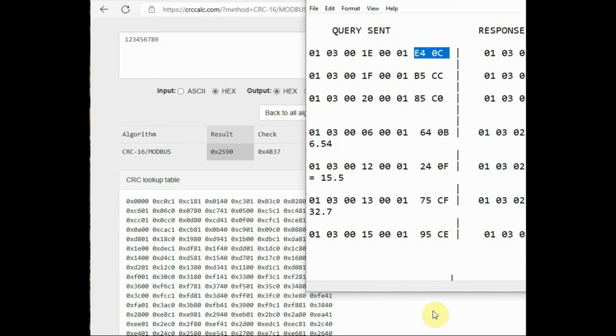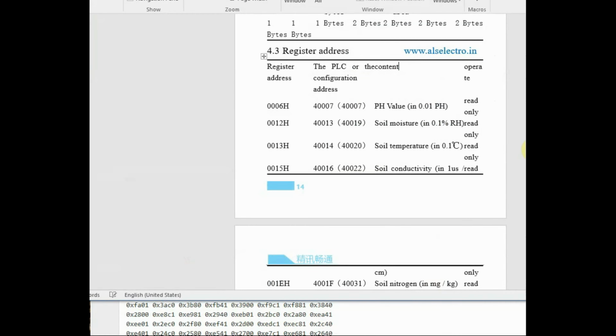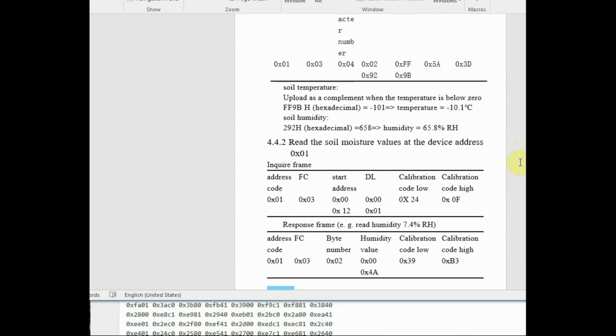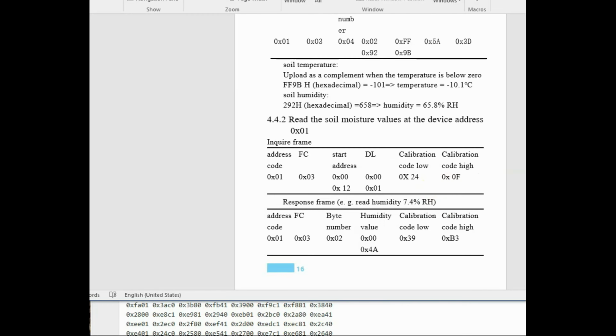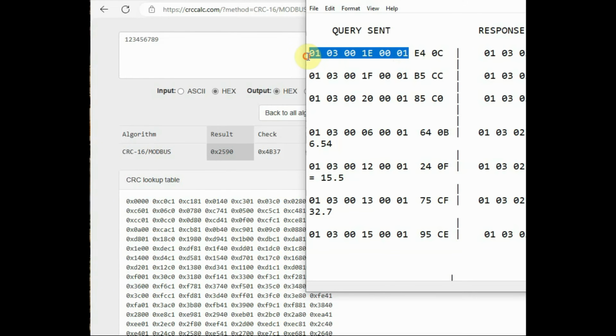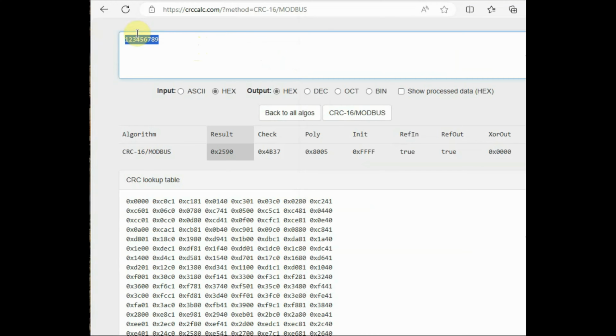Now feed in the query sent, except the last 2 bytes. Copy the query byte, that is 0103, 001E is the starting address, 0001 is the number of registers. This is for nitrogen. Copy this hex code, paste it into the website to generate the CRC16 error code.